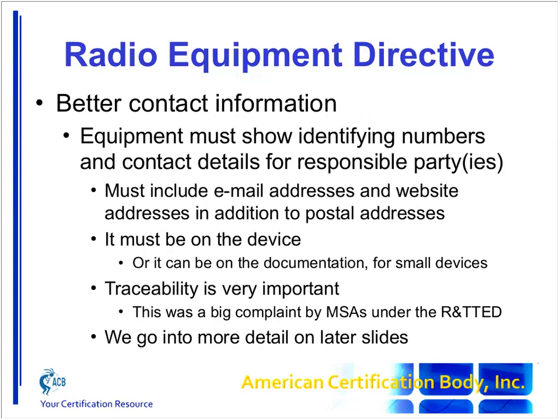For example, the name of the product would need to be on the device, but also the name and address of the manufacturer. If the product is particularly small and that's not possible, then you could put that name and address of the manufacturer on the user manual.